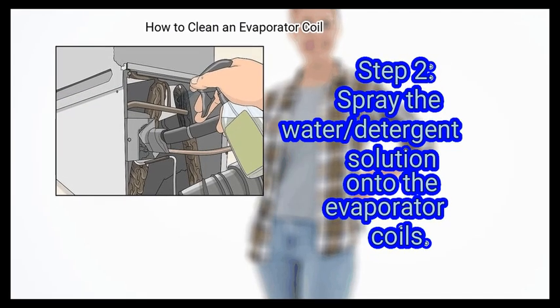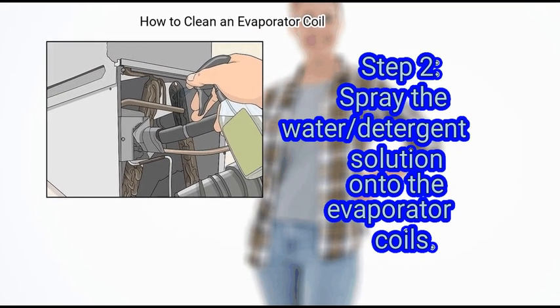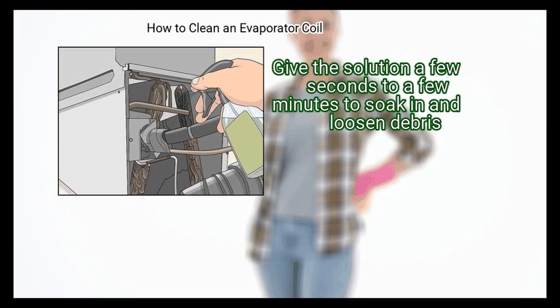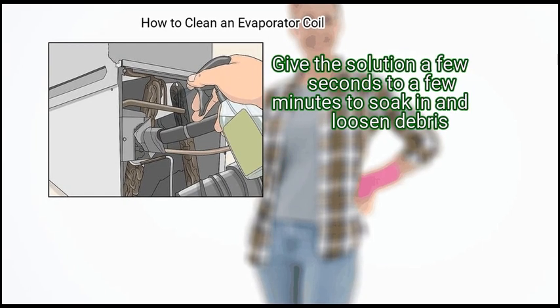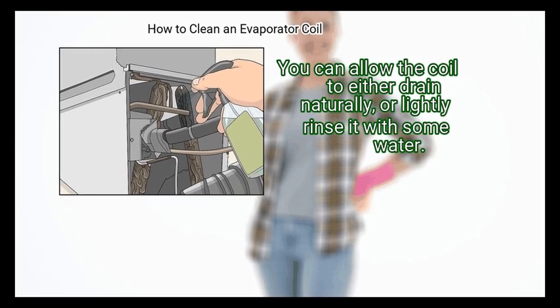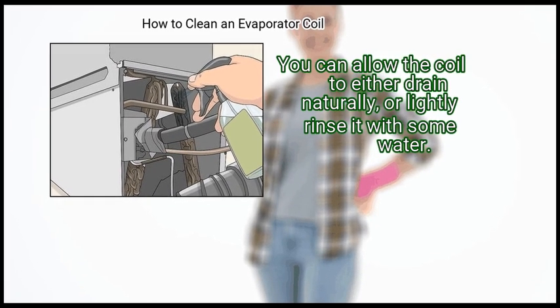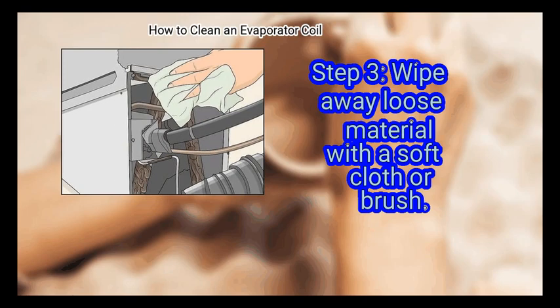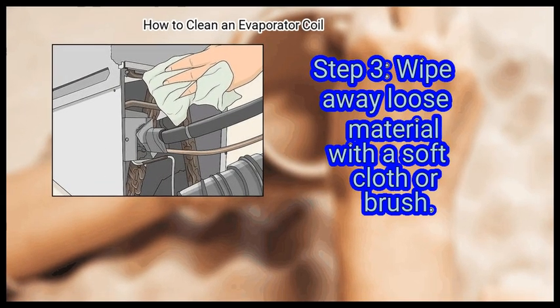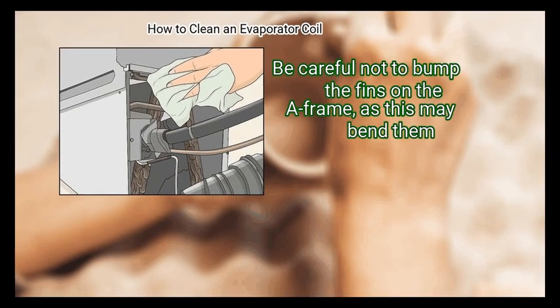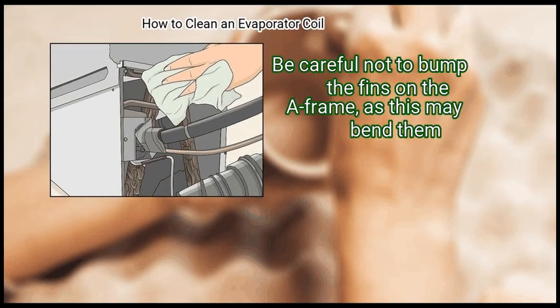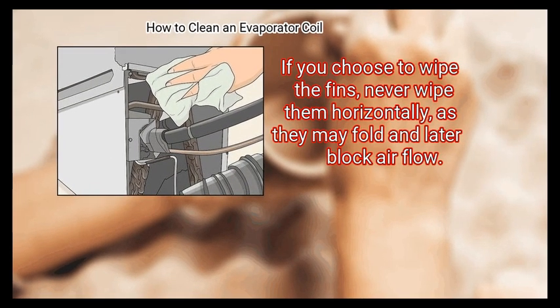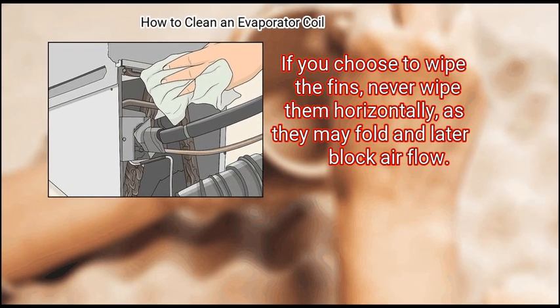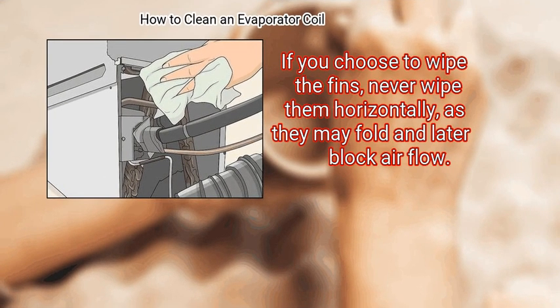Step 2. Spray the water and detergent solution onto the evaporator coils. Give the solution a few seconds to a few minutes to soak in and loosen debris. Reapply if needed. You can allow the coil to either drain naturally, or lightly rinse it with some water. Finally, wipe away loose material with a soft cloth or brush. Be careful not to bump the fins on the A-frame, as this may bend them. If you choose to wipe the fins, never wipe them horizontally, as they may fold and later block airflow.